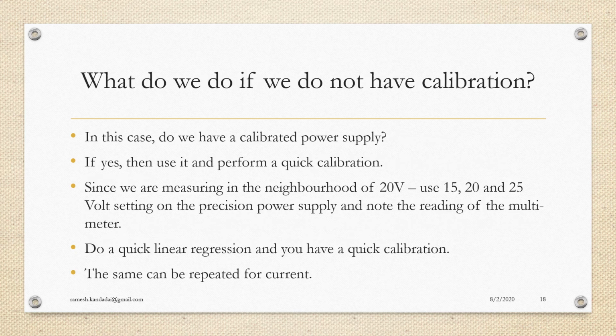If we do not have a calibration for the multimeter, the best thing is to do a quick calibration so that we reduce the uncertainty as much as possible. Since we are working in the 23 volts range, we should look at either 18, 23 and 28, or 10, 20 and 30. Take these 3 points, connect the voltage side channel of the multimeter to the precision power supply, and take readings after setting the precision power supply for these 3 values.